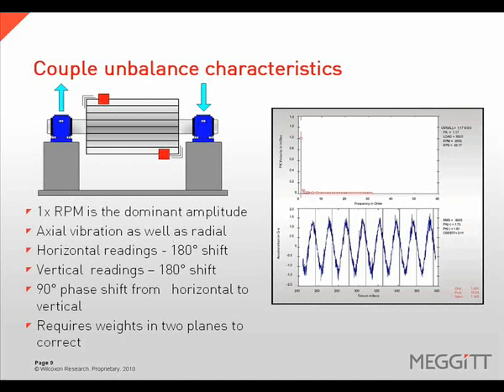Couple unbalance will exhibit a vibration response similar to force unbalance. In addition, couple unbalance will exhibit high axial amplitudes as well as high radial amplitudes. The horizontal and vertical phase readings should exhibit a 180 degree phase shift, with a 90 degree phase shift from the horizontal plane to the vertical plane. Couple unbalance will require two-plane or multi-plane balancing weight placement to correct.